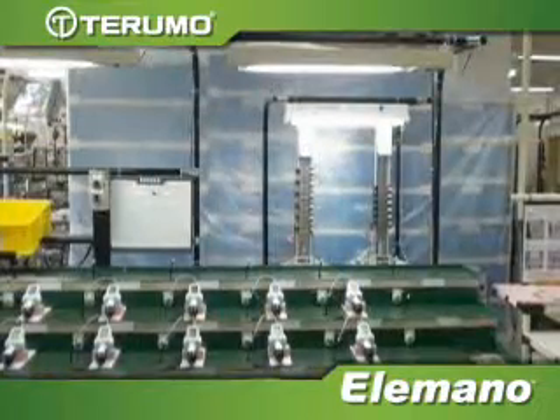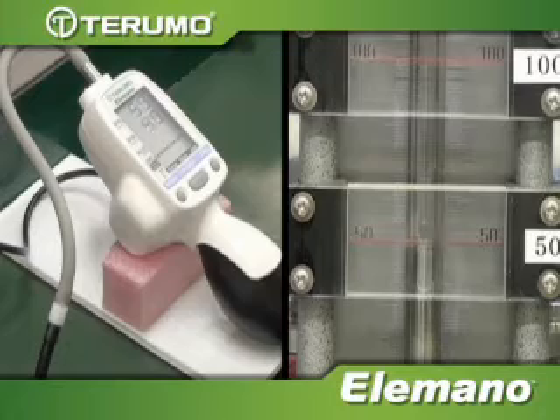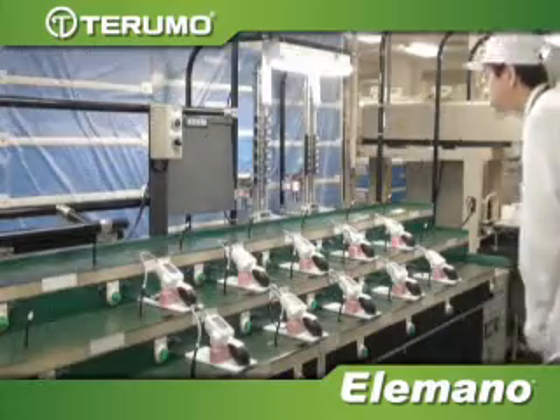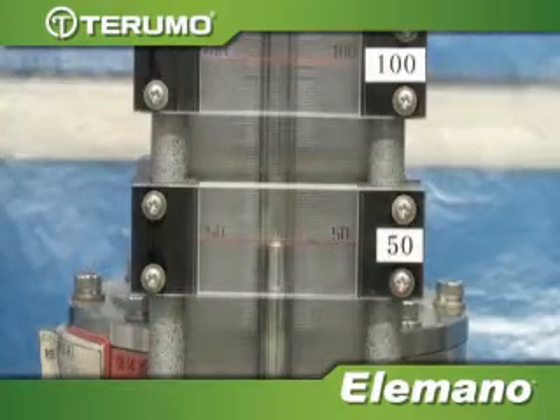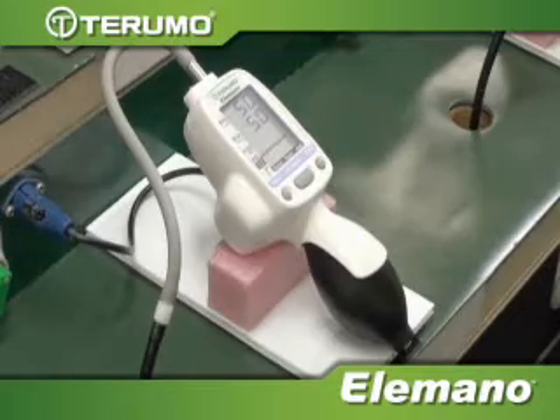Air pumps on each unit connect to one air pipe which simultaneously pressurizes both the mercury column and the Elemano monitor. The technician first checks the mercury column for the stable value, then confirms the same value on each Elemano unit before testing the next pressure level.